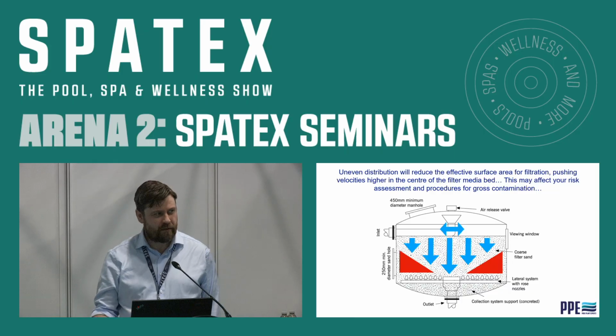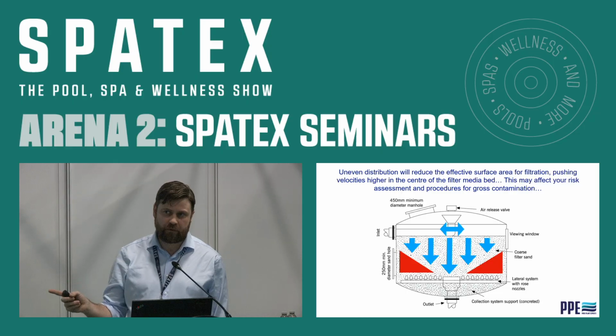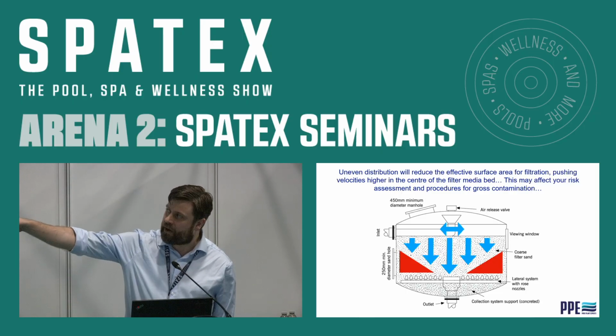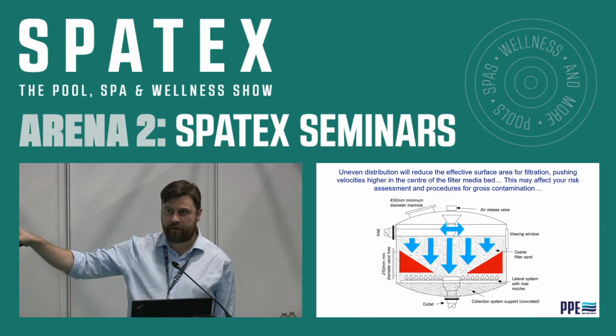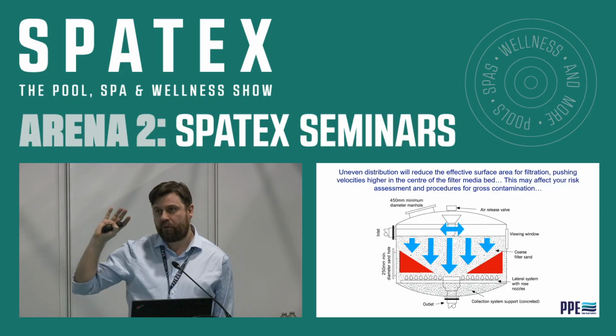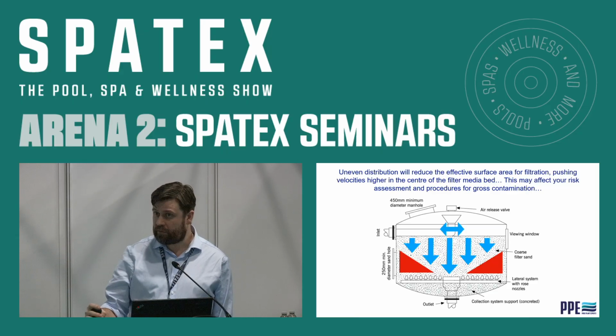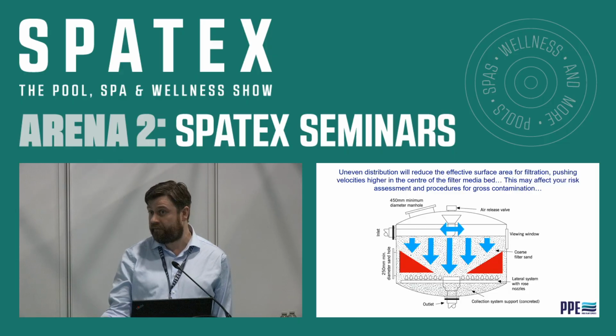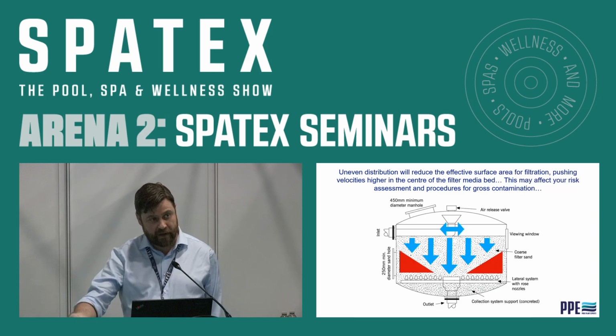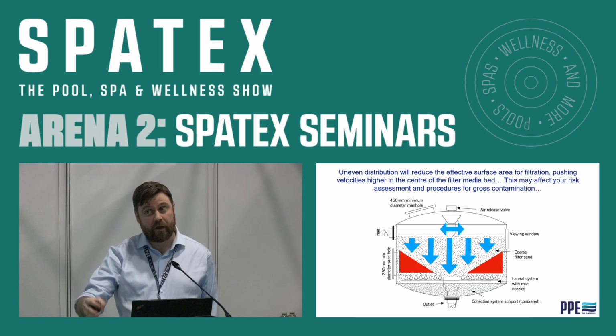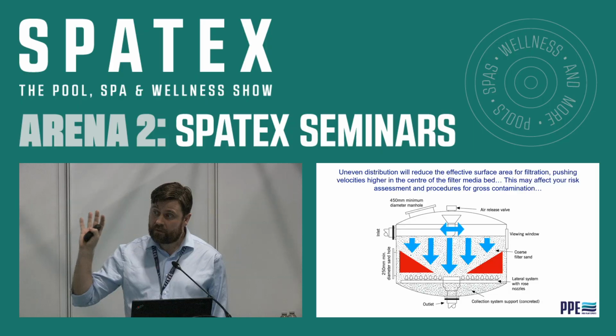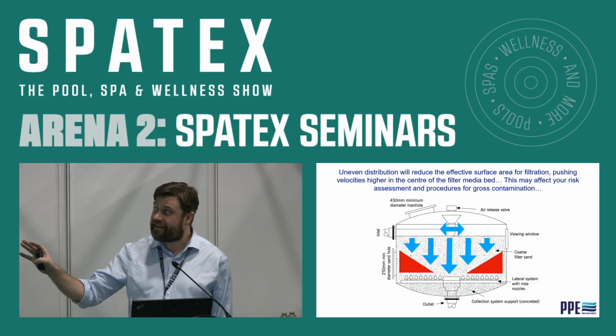It should be, but if the diffuser's too small, these two areas that are marked out in red will often become dead spots, and will either have water that doesn't flow through there at all, or even worse, every time we backwash and we get a bit of flow going into them, the water and the pollution within it stagnates in those areas, leading to an increase of biofilms and also premature lifespan for the actual media, needing to be changed.